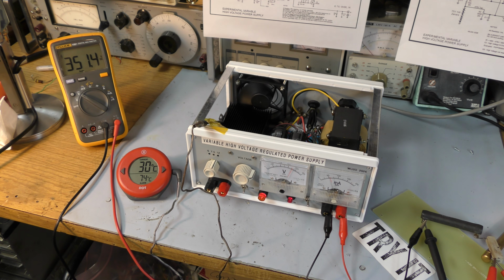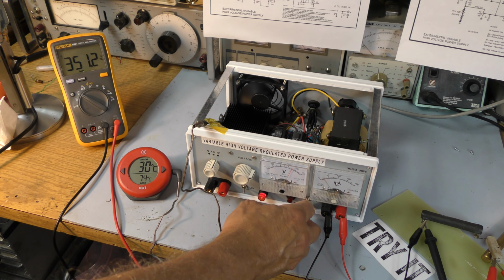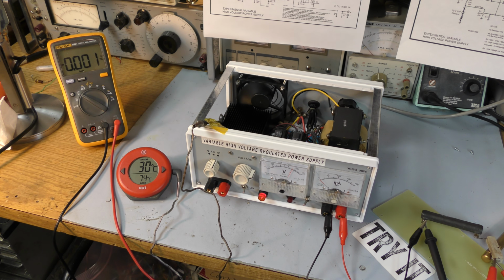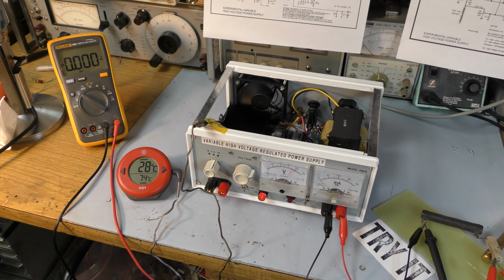So next I'm going to turn the high voltage activate switch off, and we'll see if the fan stops. I am noting that the fan RPMs are starting to go down about a minute into the activate being off. Control is smooth so far. Okay, 3 minutes into the cool down cycle, the fan has stopped.